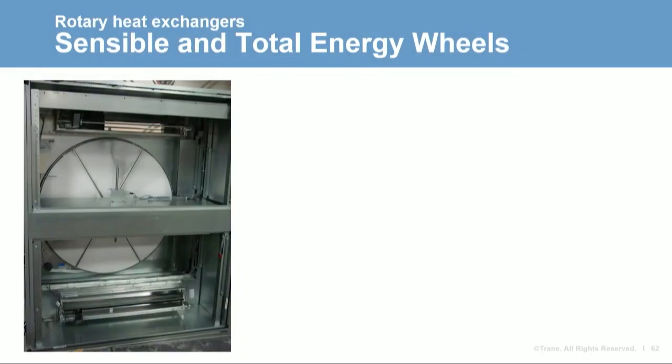The last technology to discuss is rotary heat exchangers, commonly called heat recovery wheels. Some wheels are designed for sensible heat transfer only, but most models are designed to transfer sensible and latent heat — these are sometimes called total energy wheels or enthalpy wheels. The wheel rotates between 20 and 60 revolutions per minute between the exhaust and outdoor airstreams. Total energy wheels are made with or covered by a desiccant and adsorbent that attracts water vapor, such as silica gel, polymers, molecular sieves, and others.